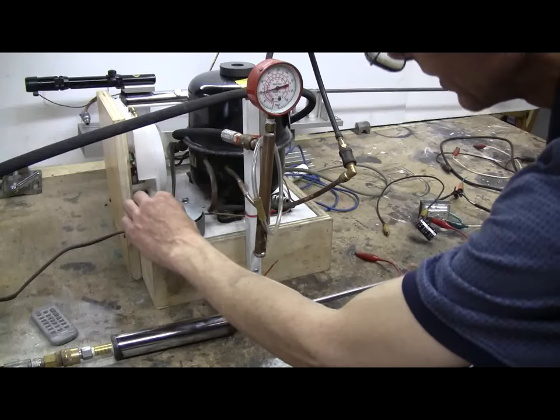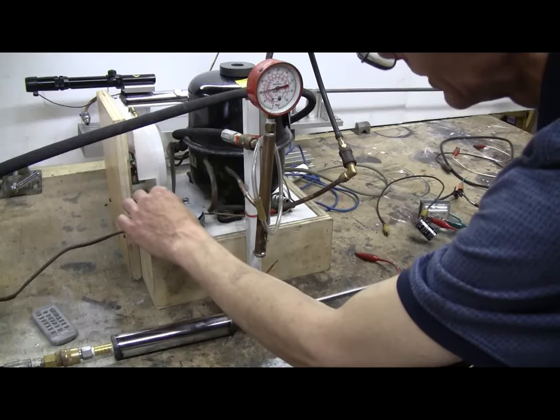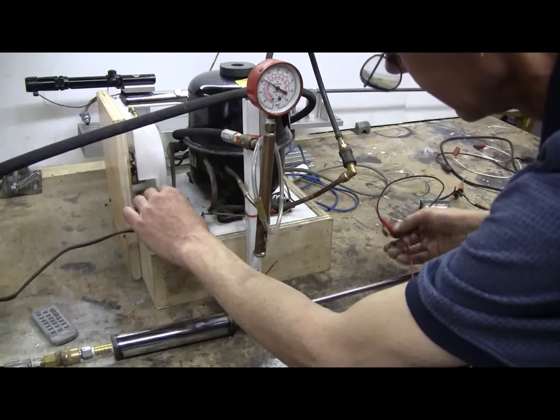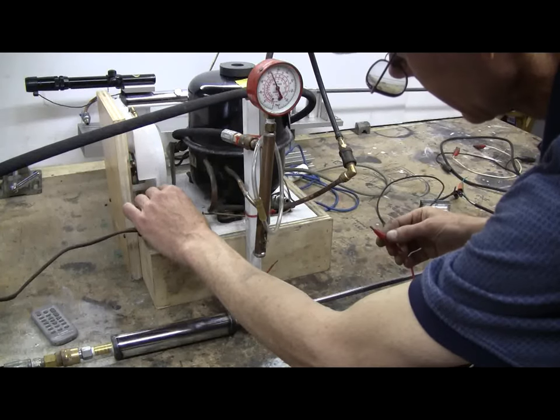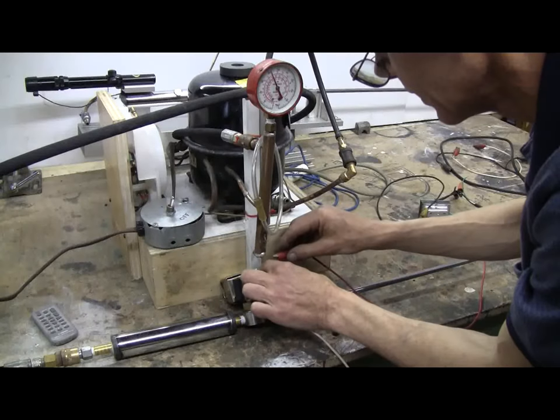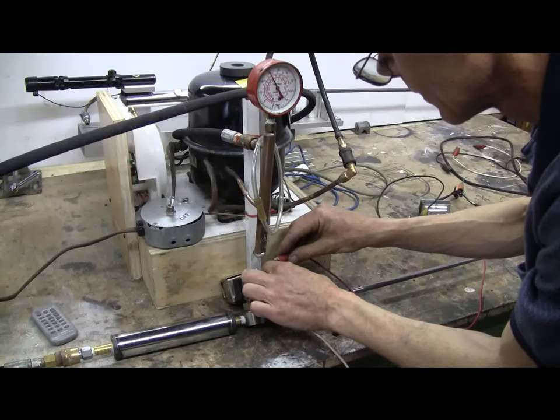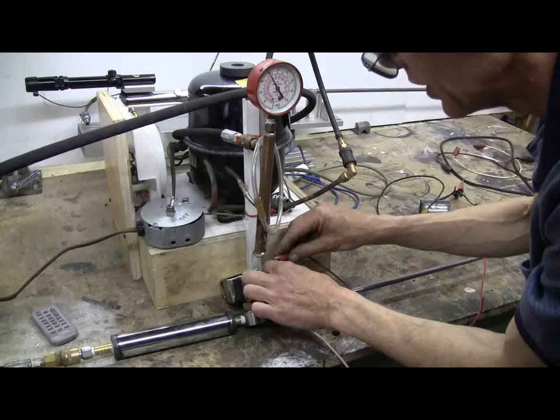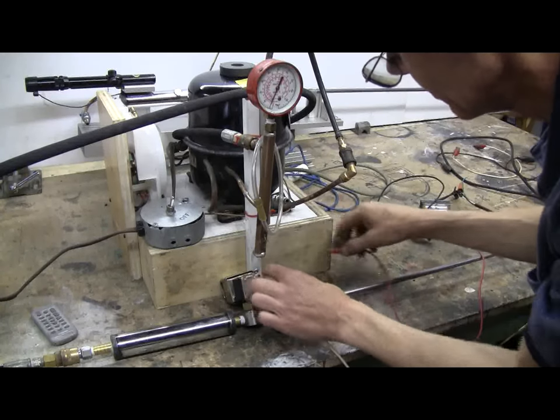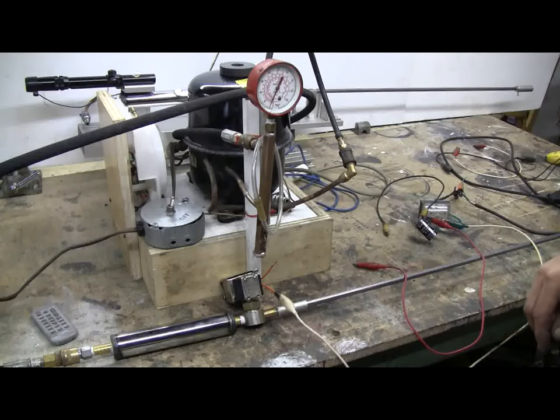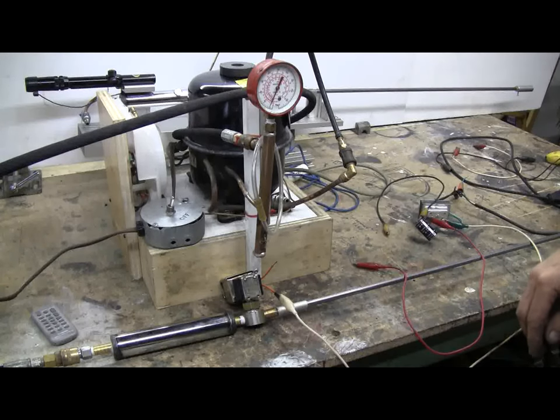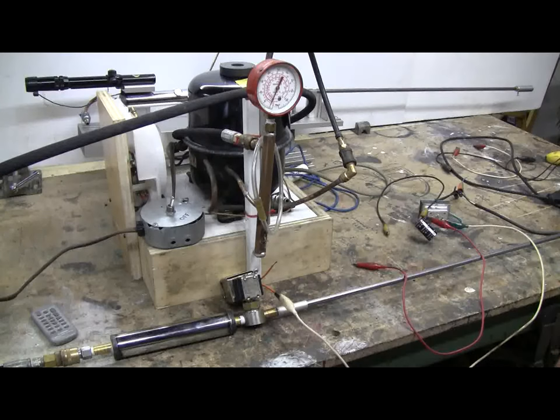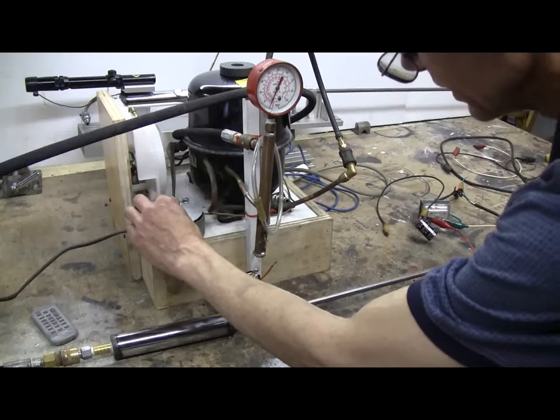Let's go to 200 psi. Again, this doesn't seem so reliable anymore. Okay, we've got about 200 psi. Valve is buzzing, doesn't want to open with AC applied. But a second touch opened it. It's not reliable now at 200 psi.